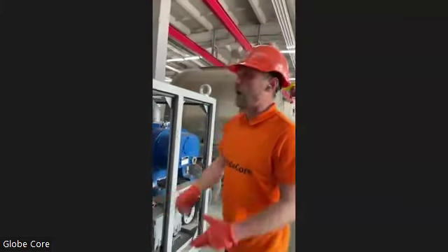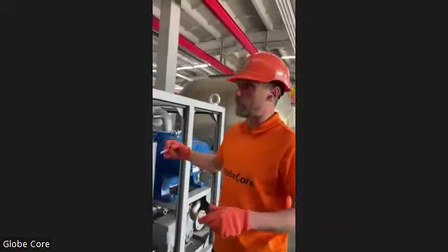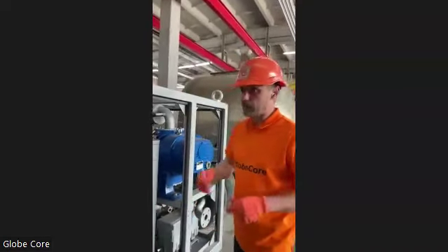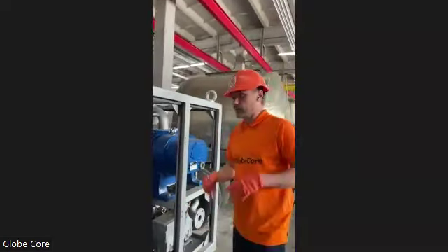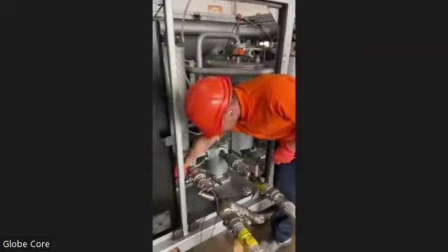After filling of the unit, you perform the internal circulation in the way I have already told you. So at first we fill the vacuum chamber with oil, then with the outlet pump, by opening this valve, we arrange the internal circulation and wait until the temperature inside the unit rises to 55 to 60 centigrades, and pressure in the vacuum chamber goes lower than 2 millibar. After that, you can start treatment of oil, taking it to the inlet and passing it to the outlet.